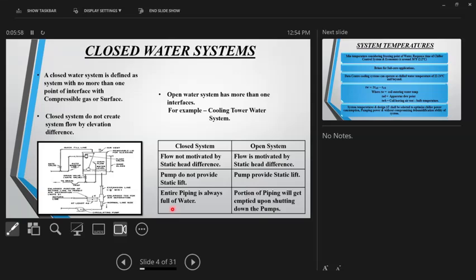In closed systems, the entire piping is always full with water. In open systems, a portion of the piping can get emptied upon shutting down the pumps. As I was saying in the first point, in a cooling tower circuit, if you switch off the pump, some of the water at higher elevation can get emptied into the cooling tower, which is not the case in closed water systems. The entire piping is always full, whether the pump is running or not running. That's why, I don't know how many of you use piping charts nowadays. Obviously nowadays there is software, but earlier in my time, 20, 30 years back, we used to use those charts. There have to be two separate charts for open systems and closed systems. How many of you have used those charts to do the piping? Those will understand that there are two different charts, and the reason is that these two systems don't behave in a similar fashion.